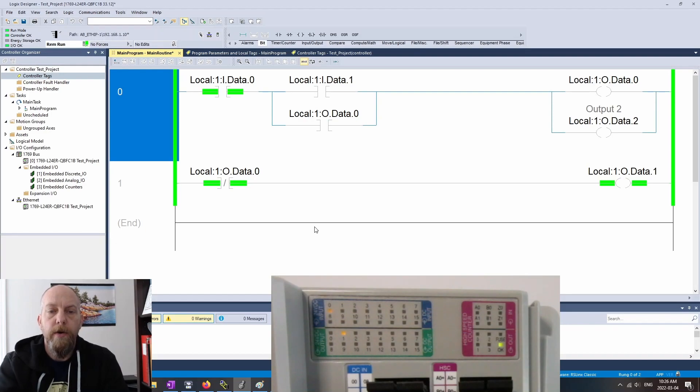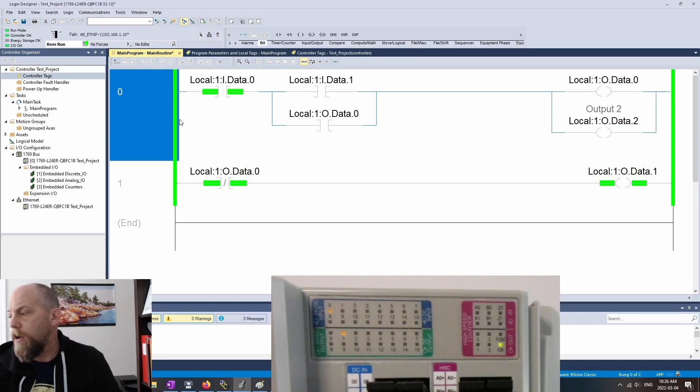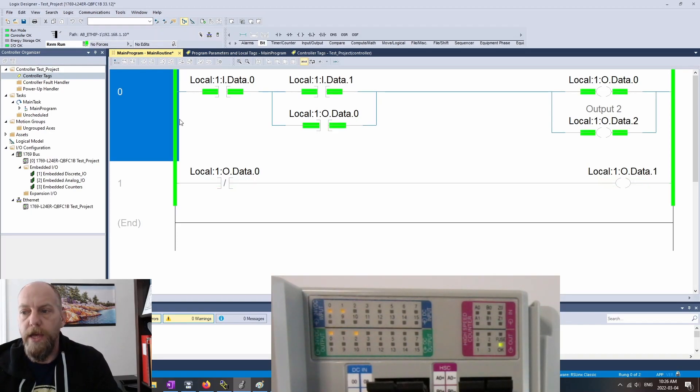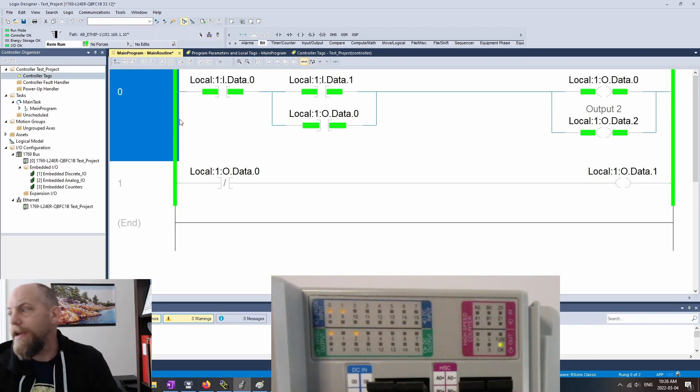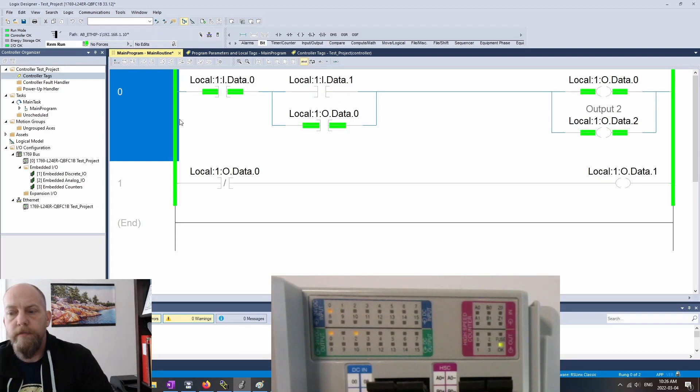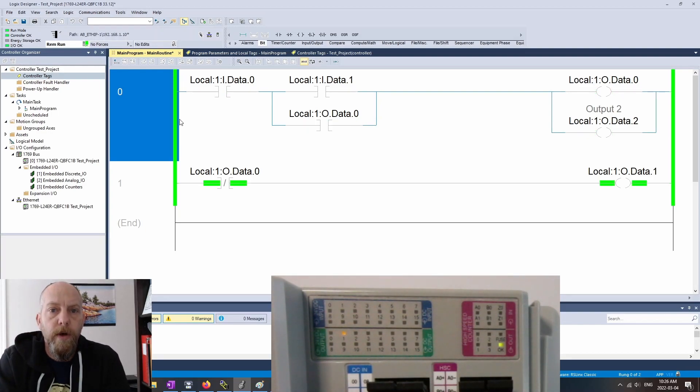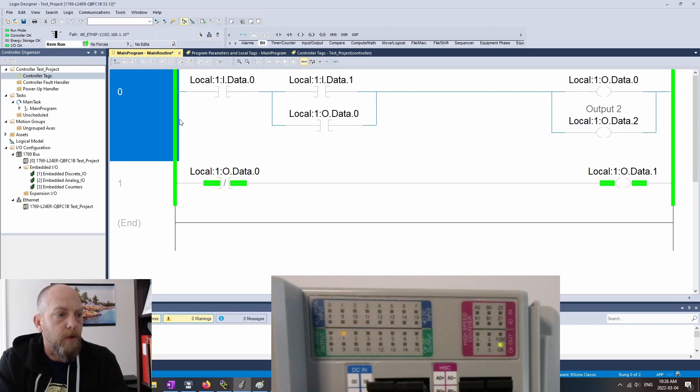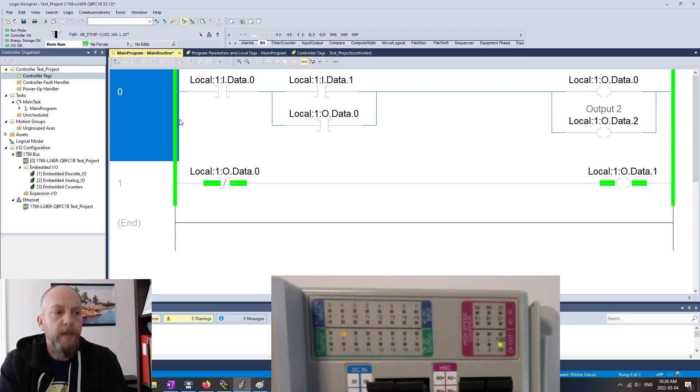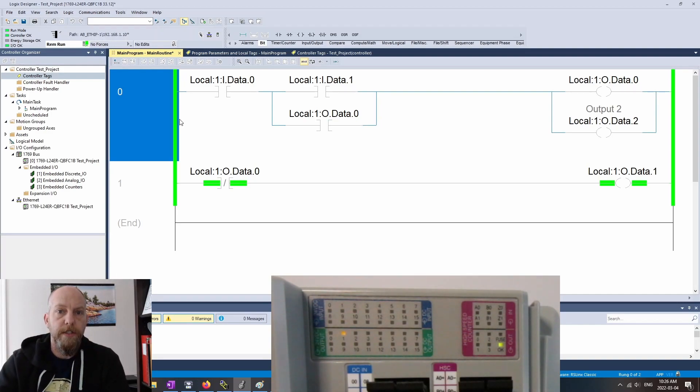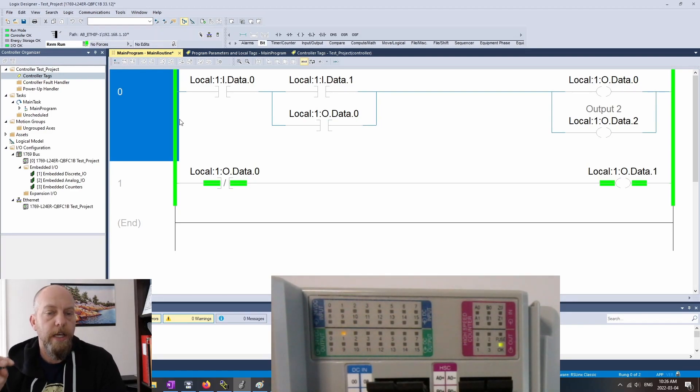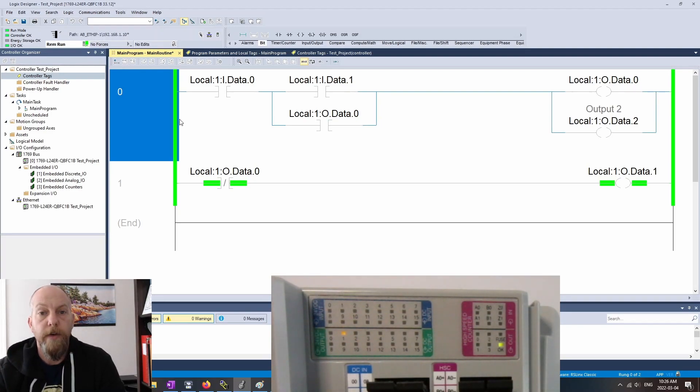Now my ladder logic, that additional rung there disappears. So now it's inserted it into that rung. And now I have a circuit now where if I hit the start push button, then both outputs, output 0 and output 2 turn on, remain on. And then when I hit the stop push button, then they turn off and output number one turns on. So hopefully that makes it a little bit more clear that you have to actually go through all those different steps in order to accept that online edit, and that the state of your outputs will not change until you've actually tested them out.